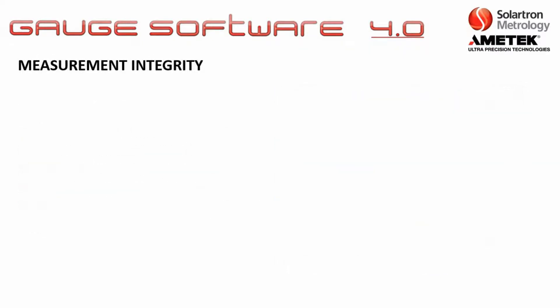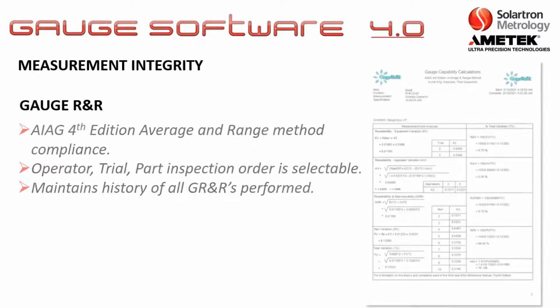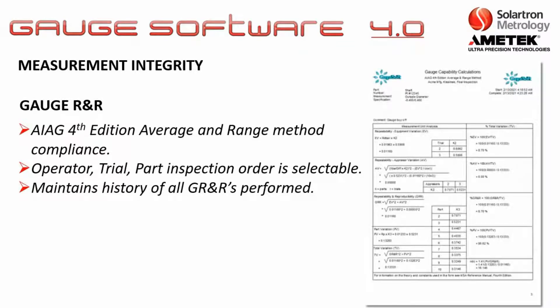For measurement integrity, there is also Gauge R&R. This software package is AIAG fourth edition average and range method compliant. You can perform Gauge R&R for operator, trial, and part inspection as you choose, and it also maintains the history of all Gauge R&R's performed.